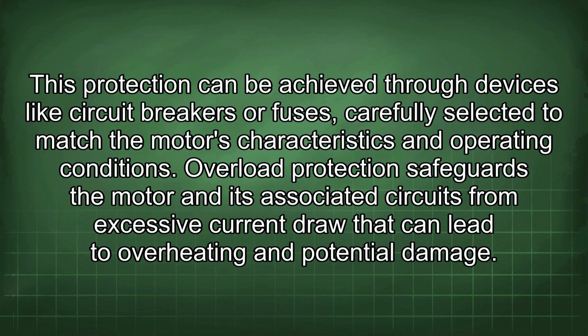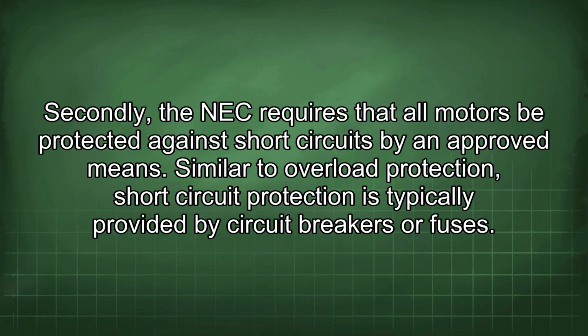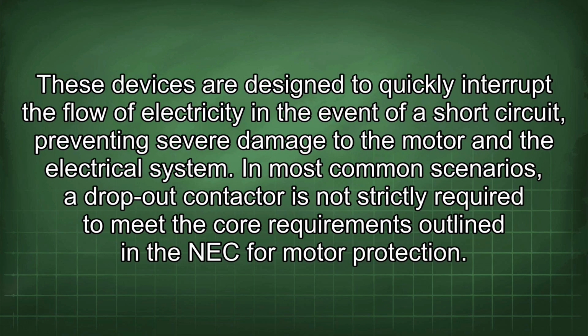This protection can be achieved through devices like circuit breakers or fuses, carefully selected to match the motor's characteristics and operating conditions. Overload protection safeguards the motor and its associated circuits from excessive current draw that can lead to overheating and potential damage. Secondly, the NEC requires that all motors be protected against short circuits by an approved means. Similar to overload protection, short circuit protection is typically provided by circuit breakers or fuses. These devices are designed to quickly interrupt the flow of electricity in the event of a short circuit, preventing severe damage to the motor and the electrical system.